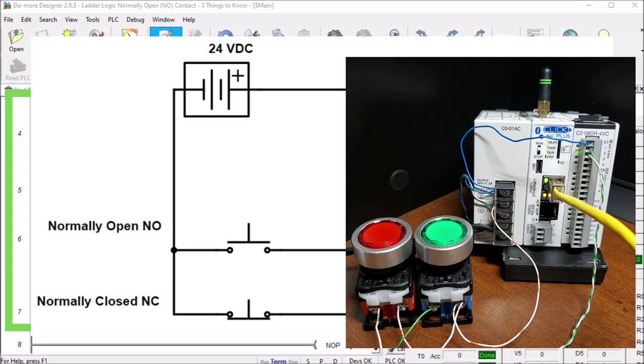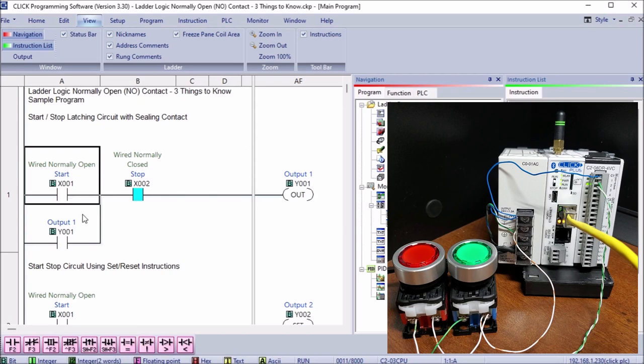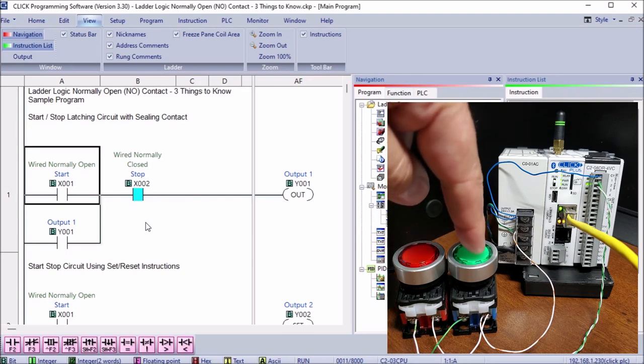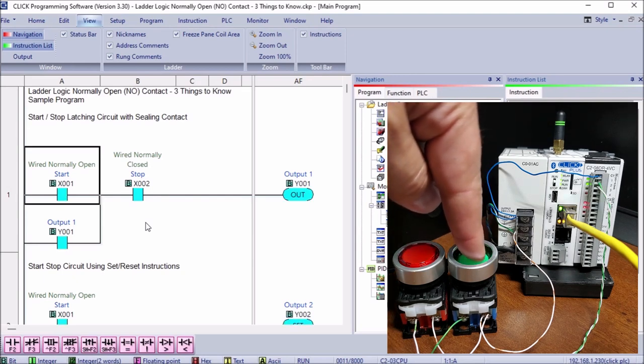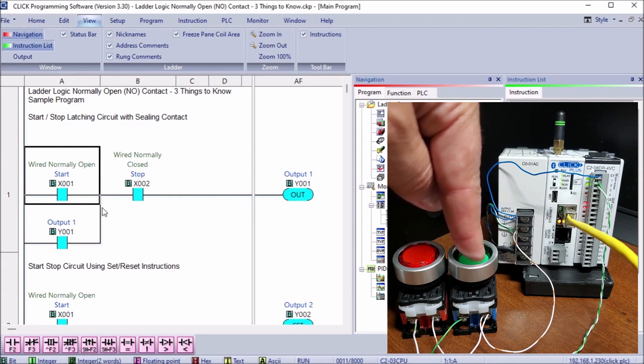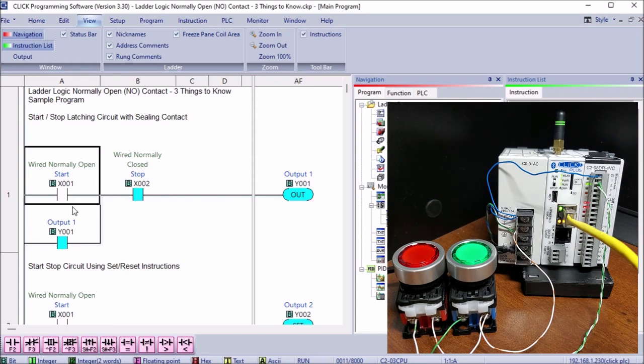Calling up our Click software, we can see that here is our software right here. Right now number two is actually on or active as we can see because we have the normally closed. If we were to hit the start, you can see that my start signal now comes on. I have my output and it seals it in using that output sealing contact in our start-stop latching circuit.